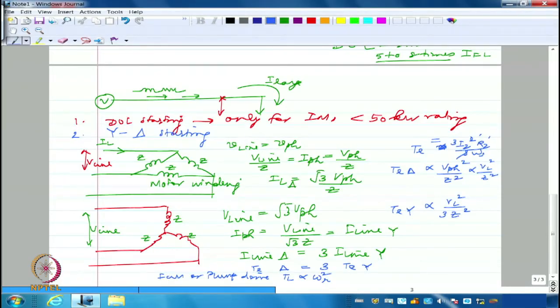So if omega R is really, really small initially, it doesn't have to displace a large amount of air surrounding it. So obviously, when I start, I will require very small torque. As I go up in speed, I will require more and more torque. So this is very much applicable to fan or pump drive, and star delta starting is very commonly used in agricultural pump sets. Star delta starters are very commonly used in agricultural pump sets because most of them require very, very small torque during the time of starting.